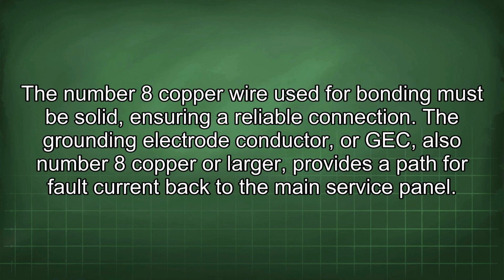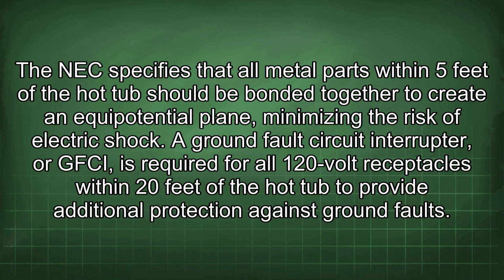The number 8 copper wire used for bonding must be solid, ensuring a reliable connection. The grounding electrode conductor, or GEC, also number 8 copper or larger, provides a path for fault current back to the main service panel. The NEC specifies that all metal parts within 5 feet of the hot tub should be bonded together to create an equipotential plane, minimizing the risk of electric shock.